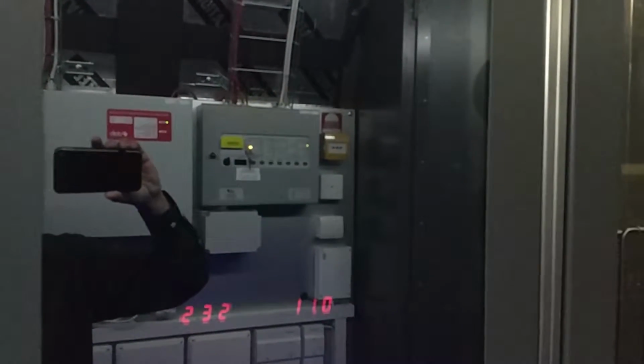This is the front of the rack. The equipment is behind a glass door. The air intake comes through these circular holes around 20 degrees Celsius. I can feel a draft coming through, but I don't think it's enough for these Antminers, which suck a lot more than what's coming out of these holes. There's some holes on the other side as well which do exactly the same thing. This is the intake. The intake comes in from the top and goes all the way down.